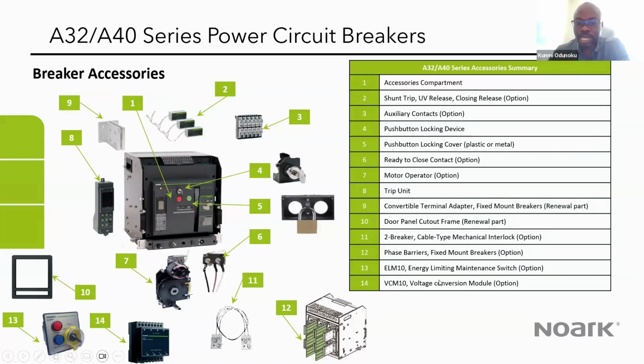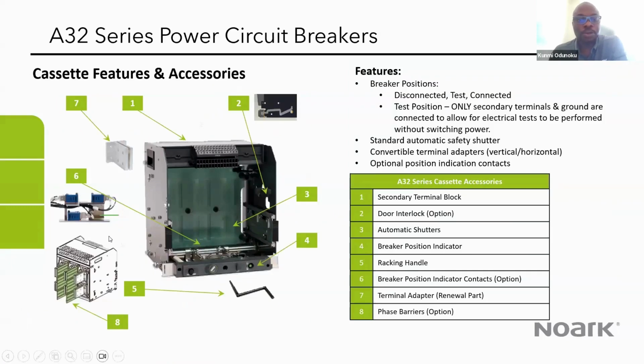We also have the VCM 10, which is a voltage conversion module. The function of this is only applicable to the A40 series, where you have the voltage going up to 800 volts. Because the trip unit is designed for up to 600 volts to be able to sense the system voltage, this device helps you to step that down to the values that the trip unit can monitor.